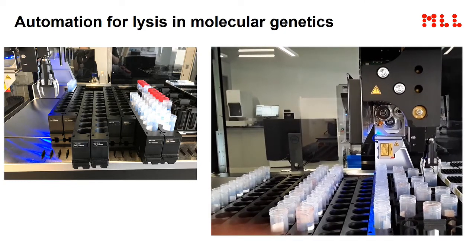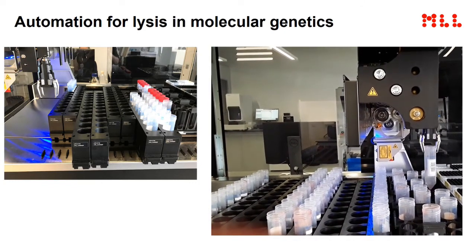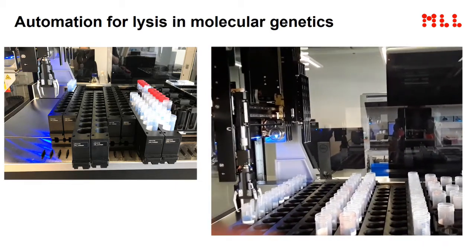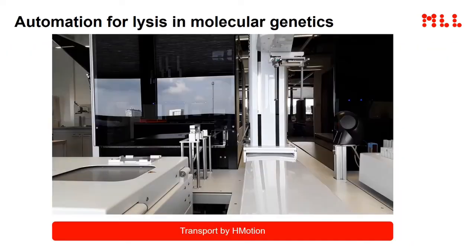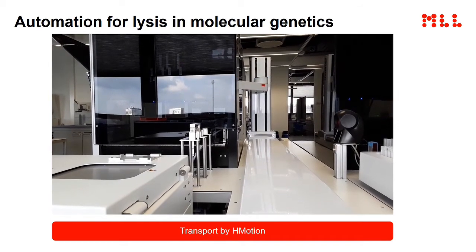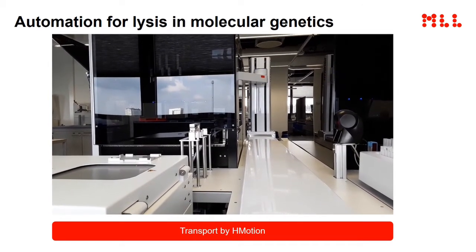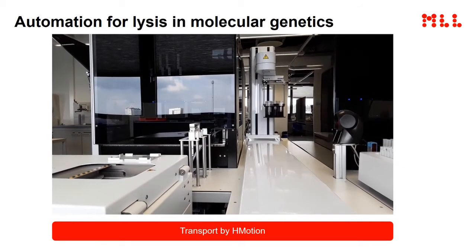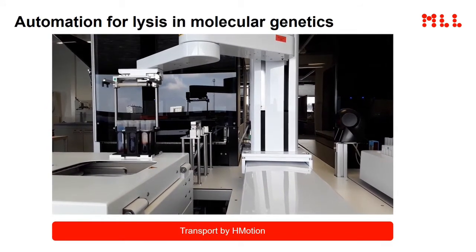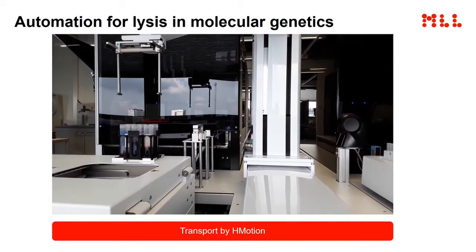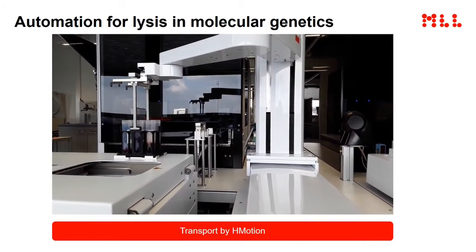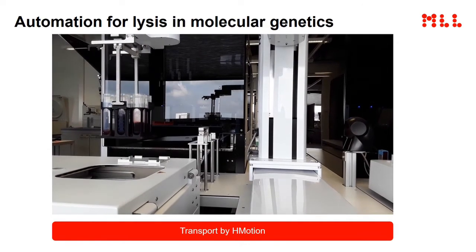And here you see the robot system we developed together with Hamilton and works with barcodes, starts here with the vials with the respective peripheral blood or bone marrow. And during several steps that are combined and connected by this H motion arm, on the left side there's a centrifuge that just opens. This robot processes the complete peripheral blood and bone marrow in a time of 2 hours from the respective sample to 2D barcoded little vials that we can finally cap and decap and then freeze in our freezers.